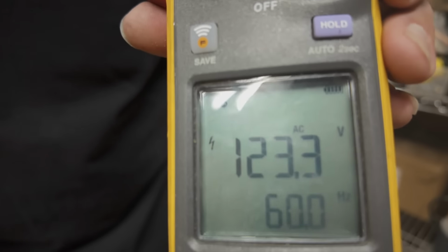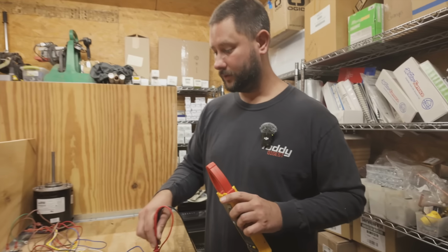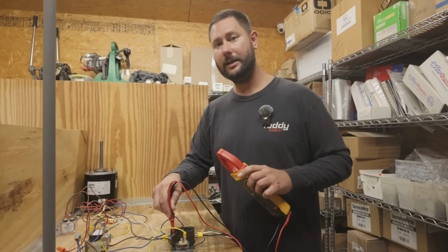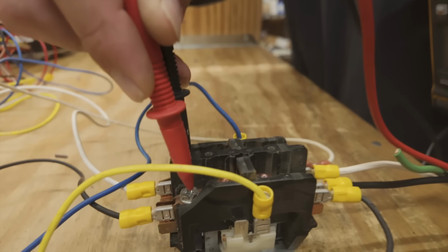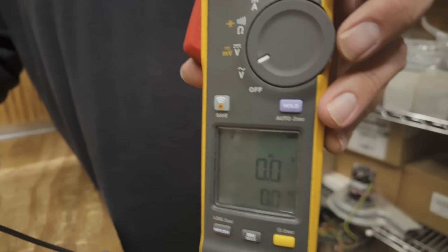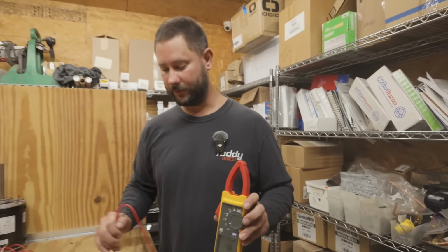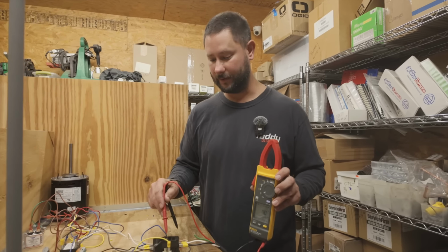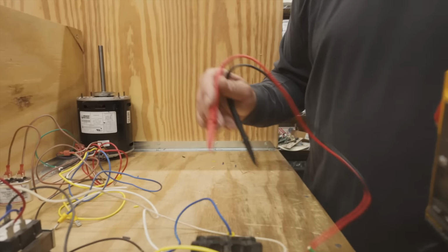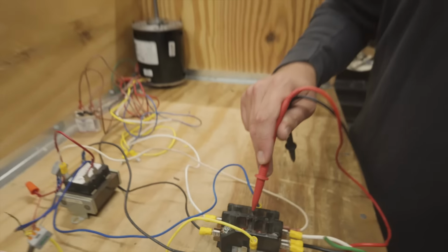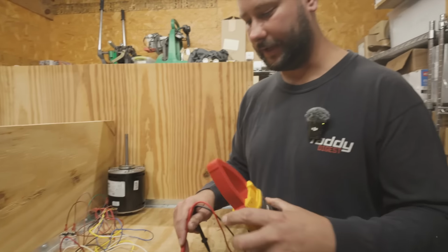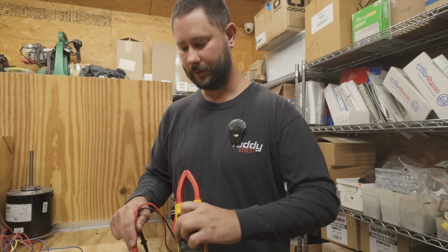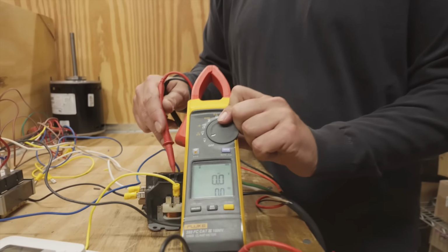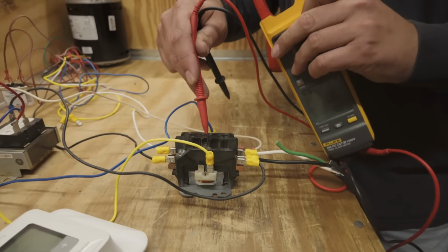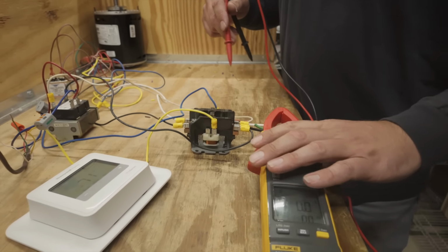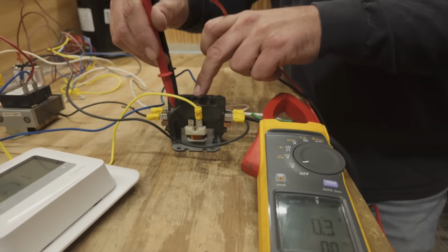See, it says 123. Now, we're not going to have any voltage on the outgoing side, or the load side, of this contactor, right? There's no voltage. There's only voltage whenever this plunger pulls in. And when it pulls in, if I push it in, our fan motor is going to be sent power. Watch. See, fan motor's running. Now, since I've got this pushed in, let me just set my meter down. I'll push it in and I'll show you on the load side.